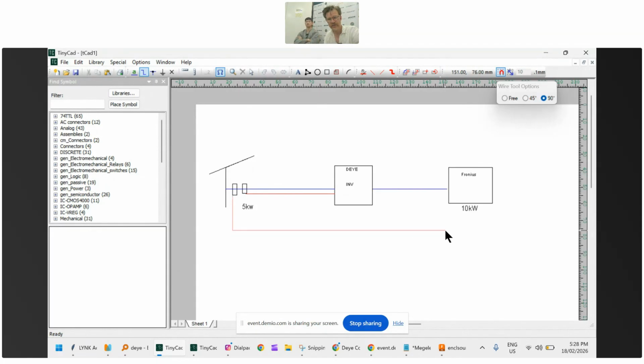And so, because the Fronius is going to need to know how much is going out to the grid, you're going to have to set up export limitation on the Fronius. When you do that, you're going to have to tell it that if it loses communication with the meter, not to ramp down to 0. Because otherwise, when the grid goes down, this meter is going to switch off. Unless you had it, I guess you could have the AC wired to the backup circuit, but normally you wouldn't. This meter is just going to disappear.